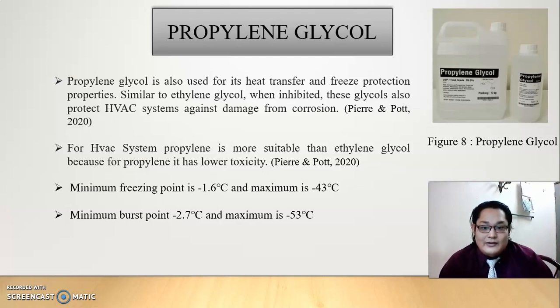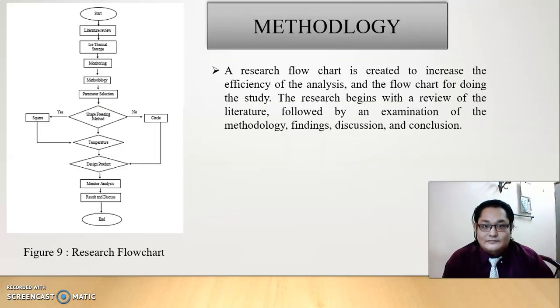Okay. The minimum freezing point for propylene glycol is negative 1.6 Celsius and the maximum is negative 43 Celsius, and it can go even lower, to negative 60 Celsius. The minimum burst point is negative 2.7 Celsius and the maximum is negative 53 Celsius.